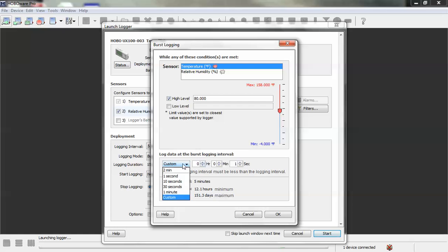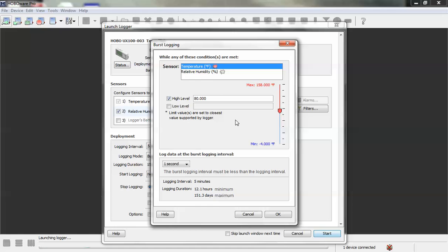So if we indeed set it to one second, what this means is that when the temperature recorded by the logger goes above 80 degrees Fahrenheit, the logger will switch from logging every five minutes to logging every second until that threshold, the temperature goes below 80 again, and then it will go back to the five minute logging interval.